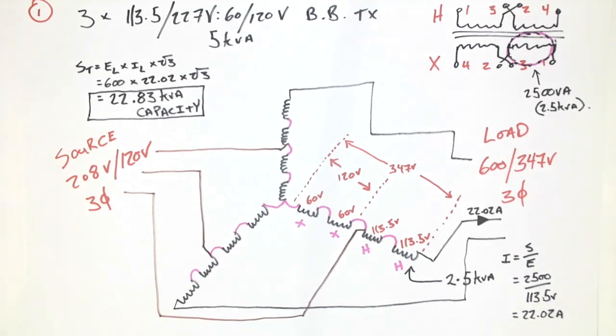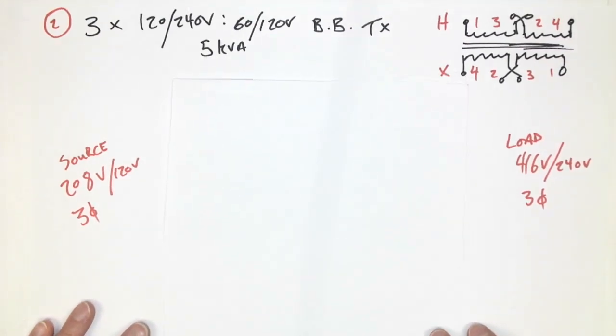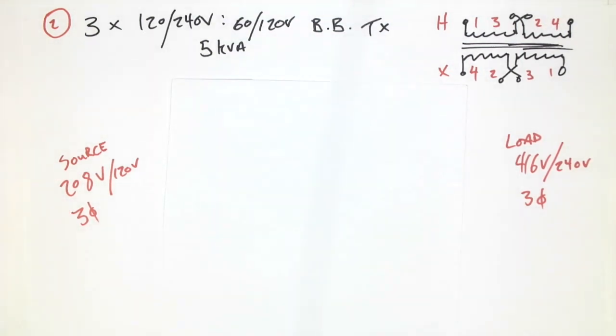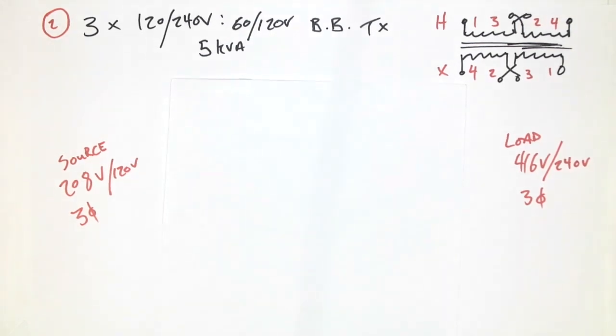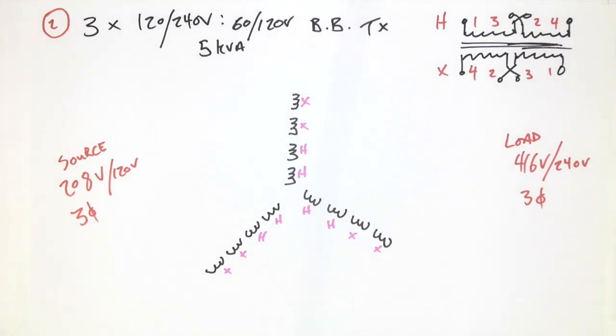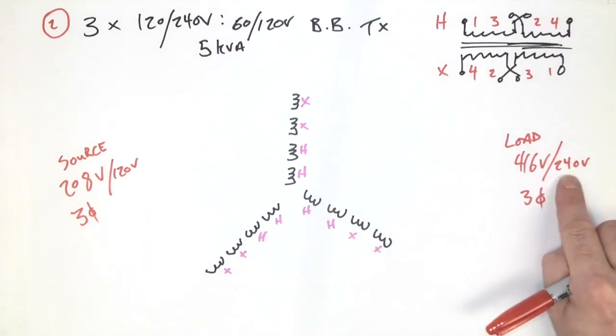This one is again going to be a Y connection. Similar transformer. The secondary is the same voltage, the primary is a little bit different. We've got that diagram again here, and I've given the load voltage of 416 volts and the source voltage of 208, and we're doing a Y connection again because we have 3 of those transformers available. First thing we need to look at is what the connection is going to look like. I'm going to sketch it out first, just as the individual windings, and then look at the individual voltages that are necessary. So we've got a 120 volt phase and a 240 volt phase.